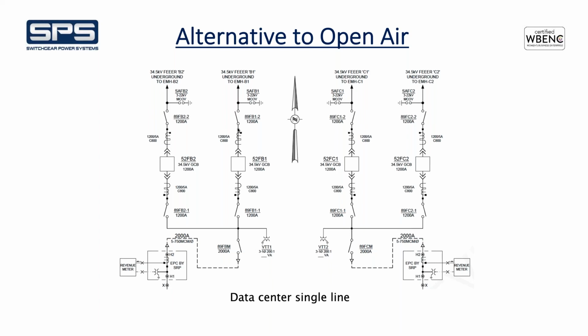One of the pros of this design, in my mind, and I've been around switchgear for a long time, and one thing I know is I think it's above 90%. It might be 91 or 92% of all arc faults that have consequences to personnel occur during the breaker racking process. Correct. And I like this design because you use the load break switch to isolate that breaker, and you're not relying on a breaker racking mechanism. Correct. Yep. That's a good point.